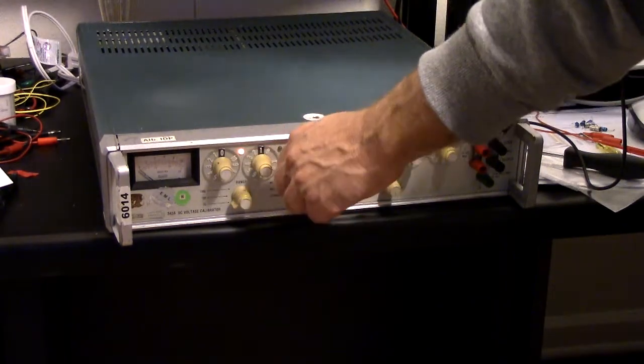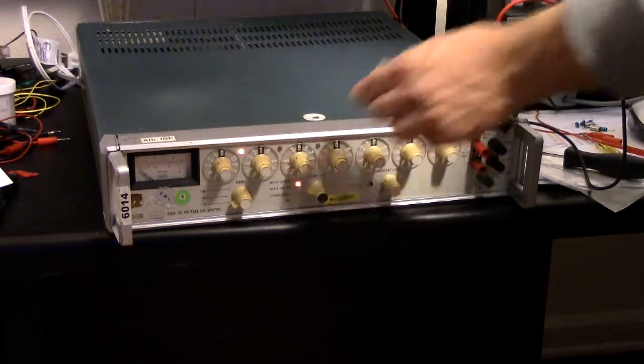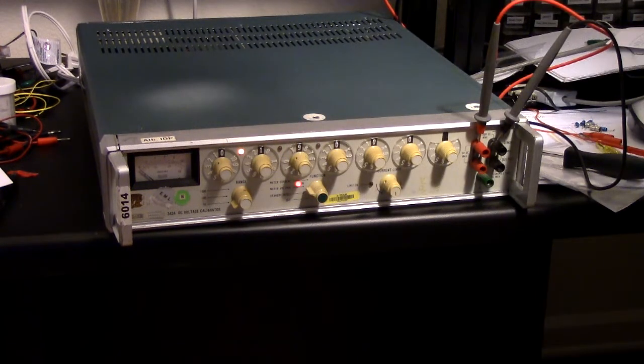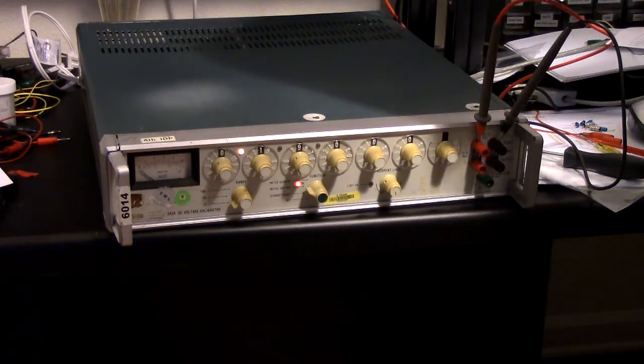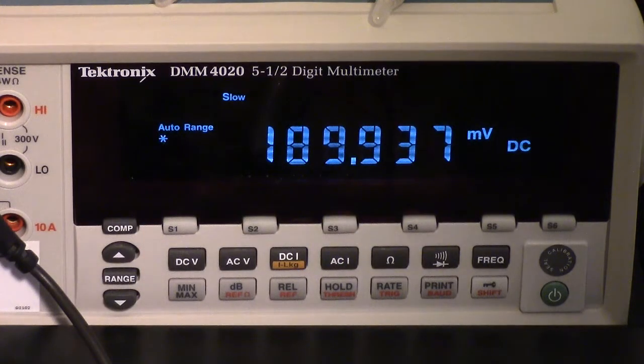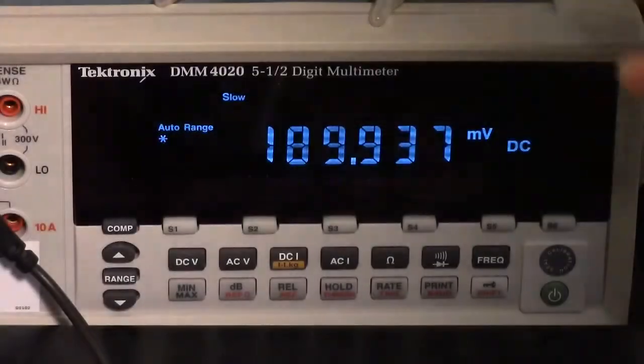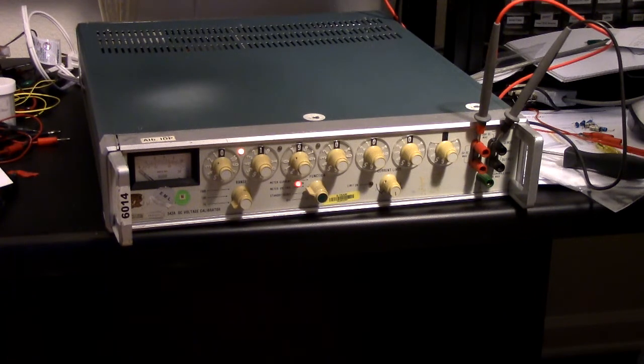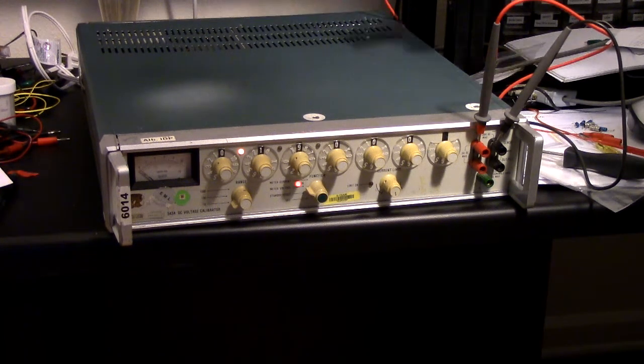The other thing is on the low millivolt range. So this is 190 millivolts, and now when it was calibrated, 190 got a reading of 190.002 as found. Anything 189.964 to 190.037 would be in spec. We're seeing 189.937, so that's out of spec. But we believe that the meter is in spec, so that would say this guy is out of spec down at those sort of lower levels.